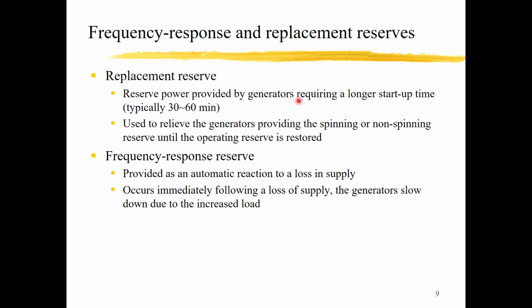What kind of generators can be started up in 30 to 60 minutes? Basically, they are natural gas powered generators. The natural gas unit can be started in a shorter time. For nuclear power, maybe you have to start for many days, and for a coal generator, it may take one day to start up the system. For an oil system, maybe a few hours. But natural gas is the fastest among the fossil energies.